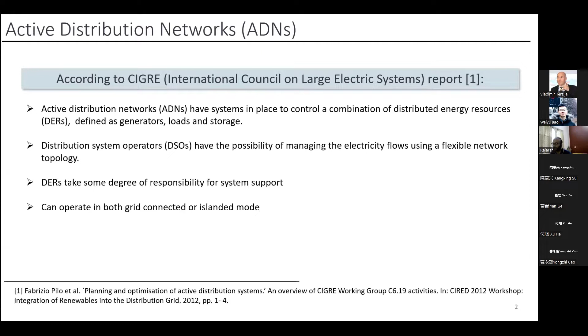So what are the challenges in such a system? This is basically the difference between a conventional passive distribution system and an active distribution system. In the passive distribution system, the power flow was basically unidirectional, and as a result the voltage profile would decrease gradually as we traverse nodes farther from the substation. However, in an active system, there can be bidirectional flow of power, and as a result the voltage profile can be quite different from what we have experienced previously.